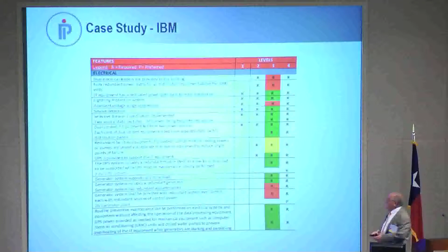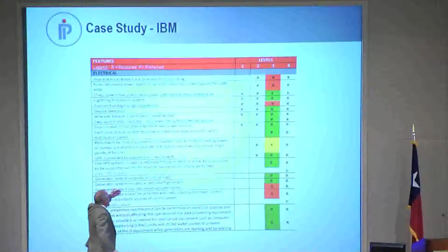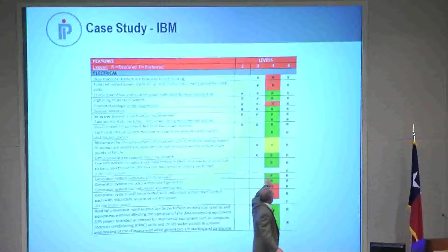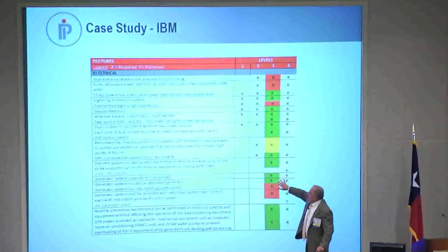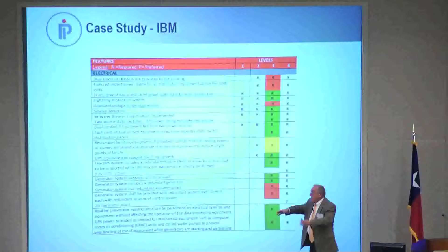For example, one requirement is that the generator system includes a redundant generator. That's not required in Tier 1 or Tier 2, but here they met it. On another, the generator system needs all of the redundant appurtenances, dual starters, dual filters, and other elements. So although they had the redundant generator, it didn't necessarily have all the redundant elements on the generator. That's typical of what we'd review electrically.